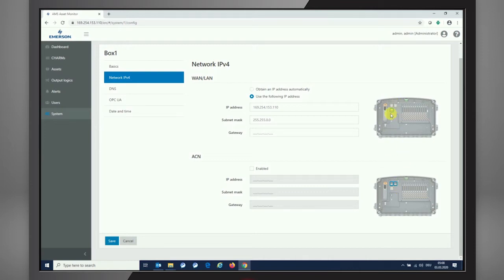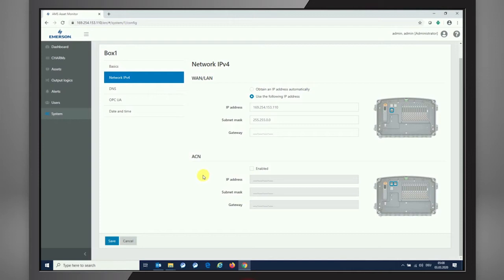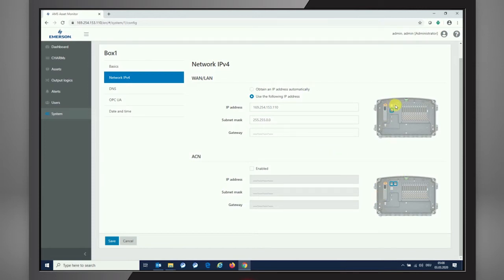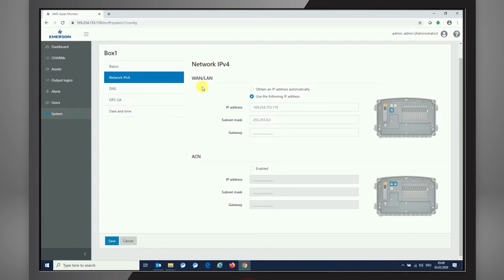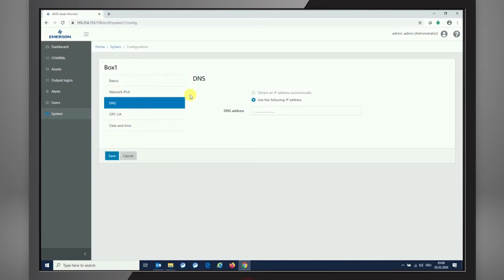With different IP addresses for being integrated into different networks, but finally providing the same data of information. It's just the speed that is limited to 100 megabits for the upper two RJ45 TCP/IP connections and one gigabit for the lower one. Further to that, we're having DNS settings that can be automatically addressed, or if we are using a DNS server, it can be entered over here.